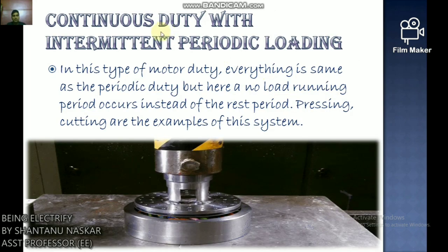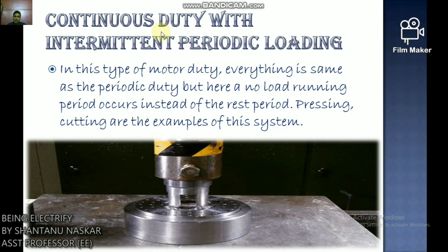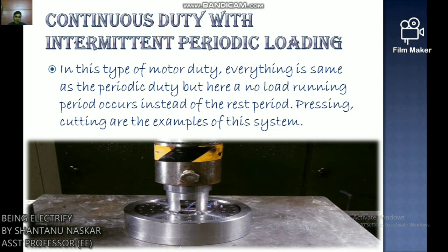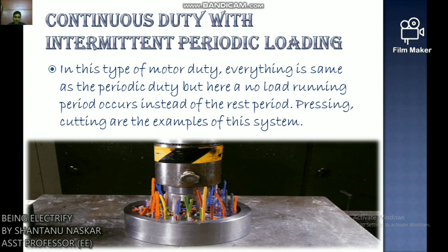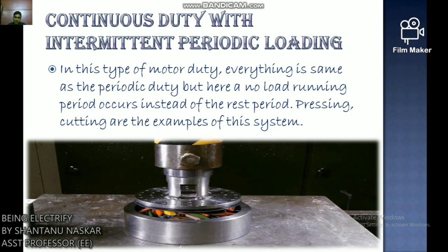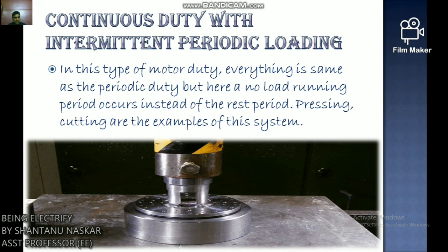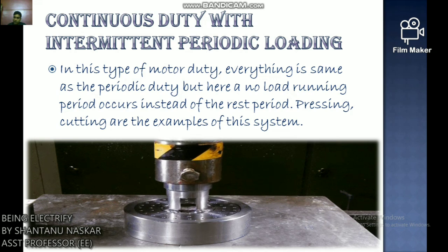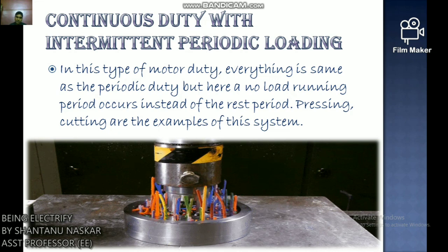Continuous duty with intermittent periodic loading: Everything is the same as intermittent periodic duty, but there is a no-load running period instead of a rest period. Pressing and cutting operations are examples of this system.